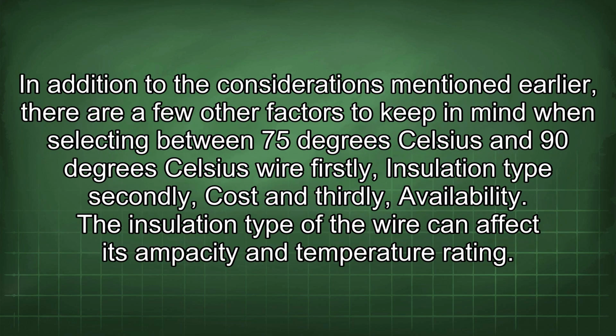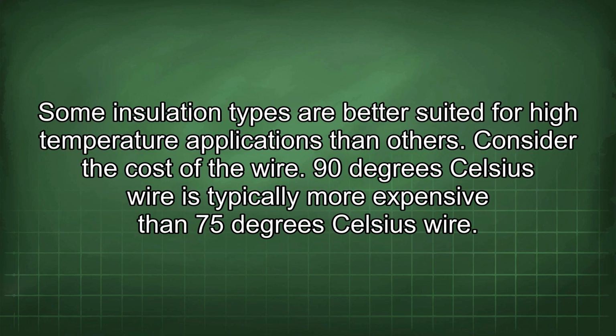In addition to the considerations mentioned earlier, there are a few other factors to keep in mind when selecting between 75 degrees Celsius and 90 degrees Celsius wire. Firstly, insulation type. Secondly, cost. And thirdly, availability. The insulation type of the wire can affect its ampacity and temperature rating. Some insulation types are better suited for high temperature applications than others.